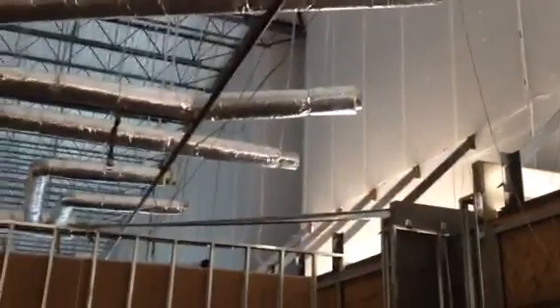Now, I made reference to the slot diffusers. Let me get through this wall here. Okay, that's this conference area — it gets a hard ceiling in here. This is where we're going to have a little bit of discussion with the framers about getting our frames sized properly to support our slot boxes. There's only four of them in here. The layout looks kind of off to me, but it's per plan — with having four on that side and none on that wall, which I find a little unusual, but I didn't design it.